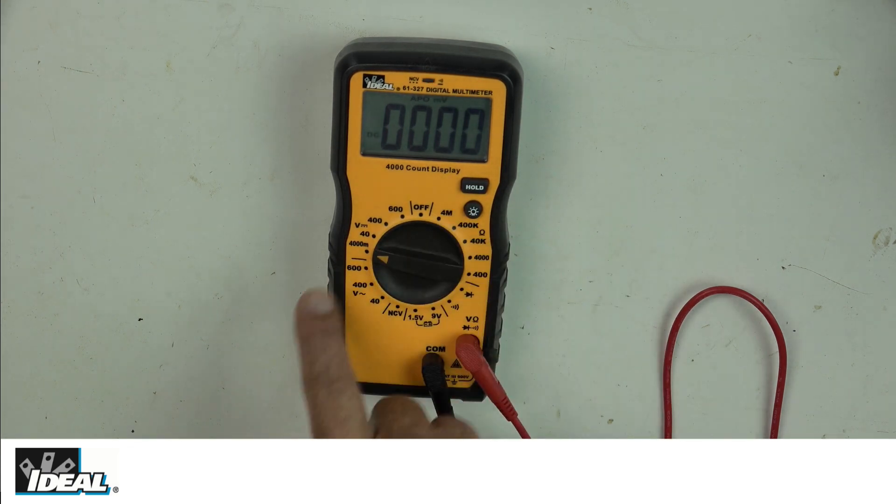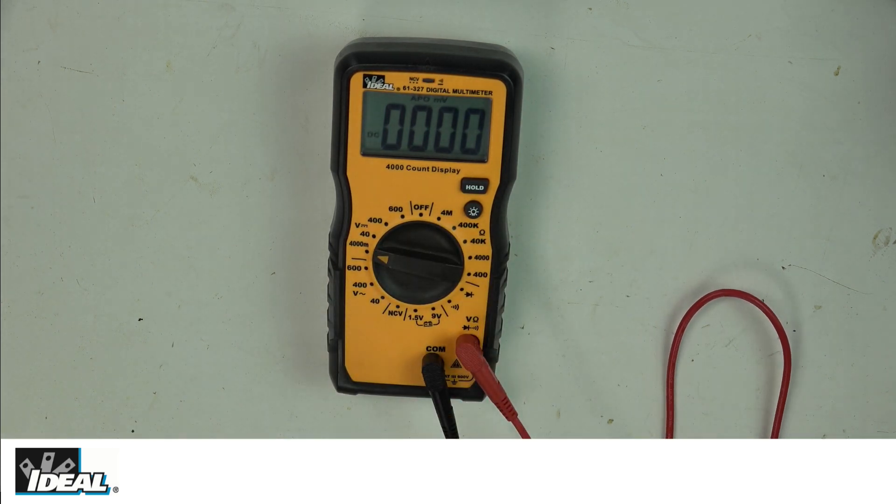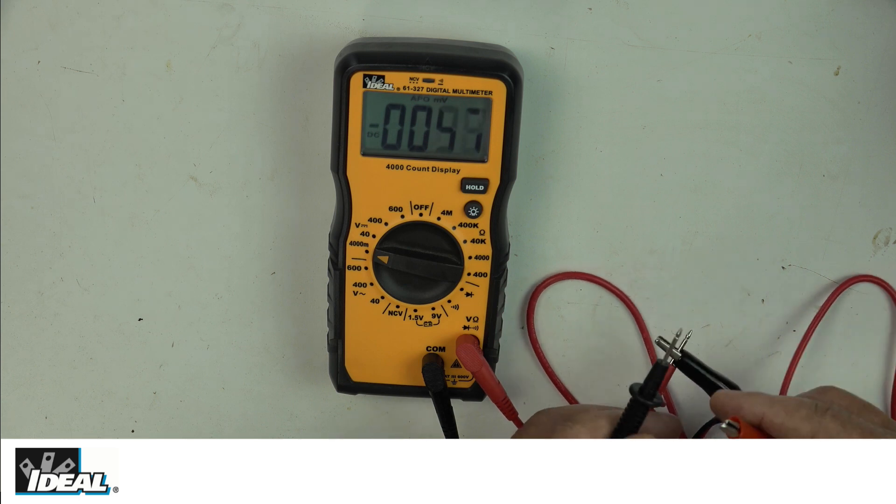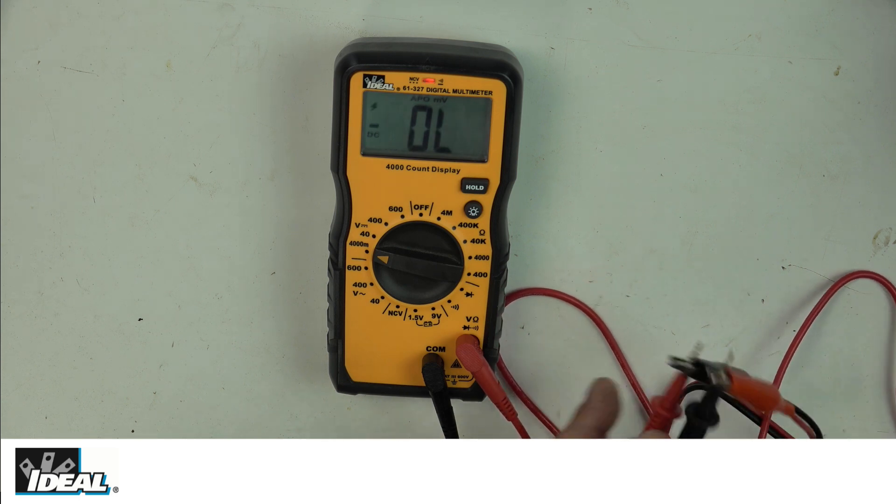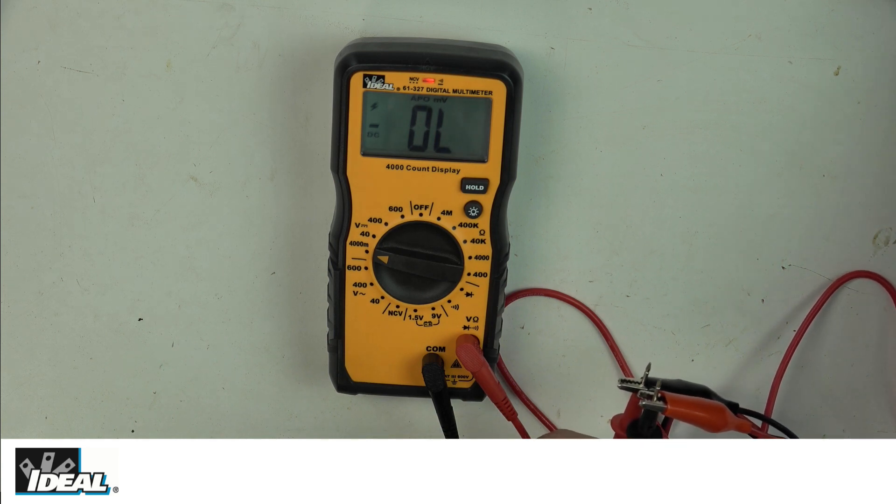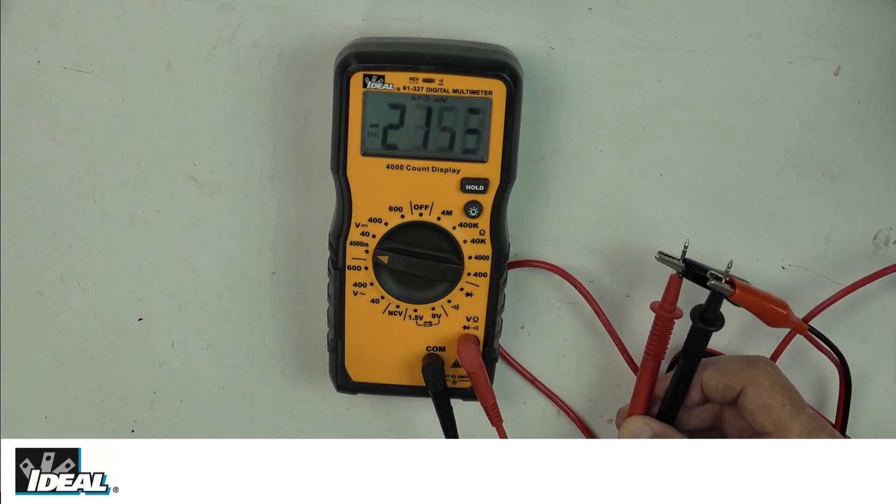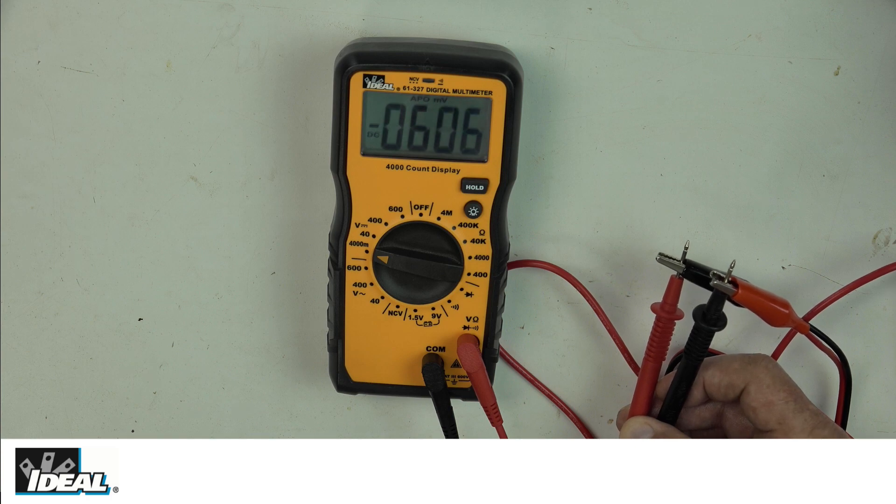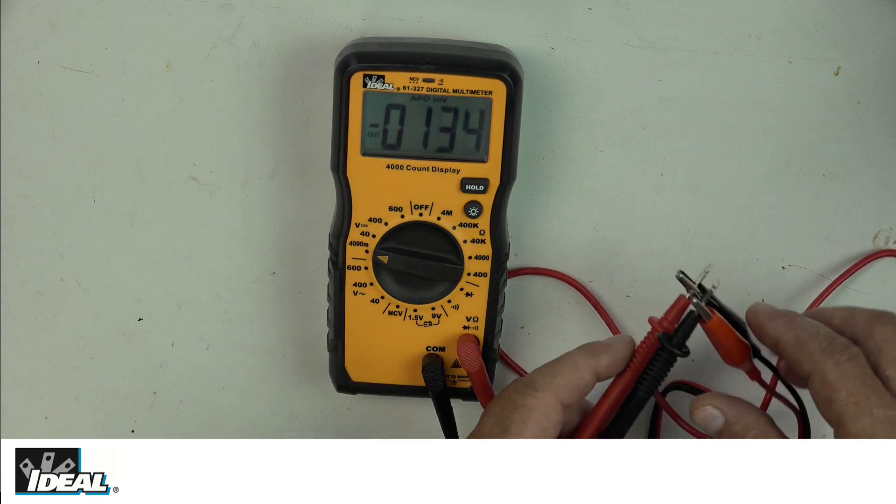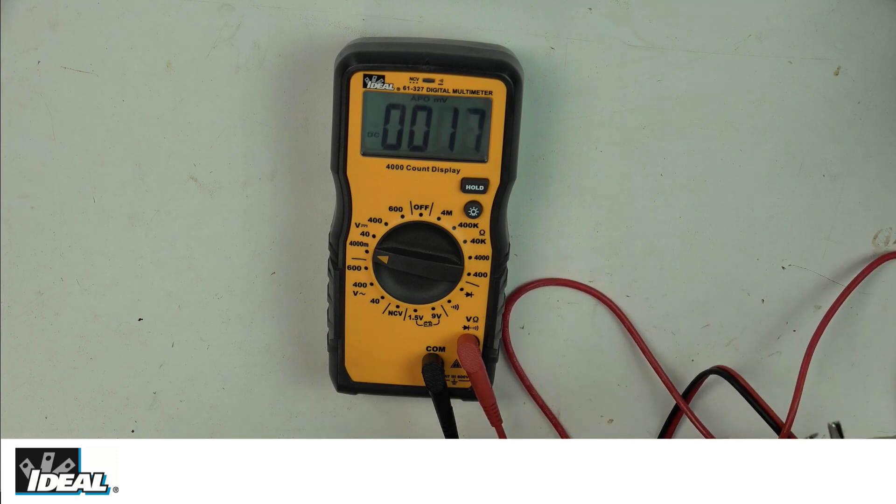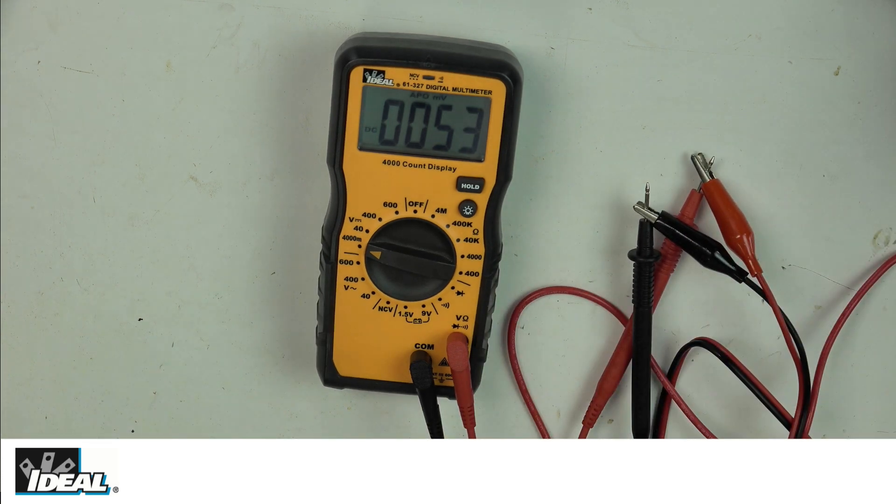I'm going to measure some DC voltage. I'll set it to its lowest setting, which is 4000 millivolts. If I incorrectly put the test leads on the tester - let me crank my power supply down. It's measuring millivolts and giving me a negative sign, which means I have my test leads with incorrect polarity. So I'm going to correct that. Now we're reading around 50 millivolts.